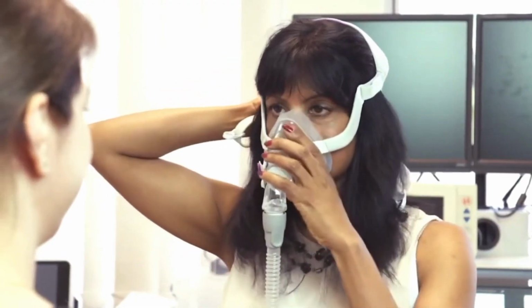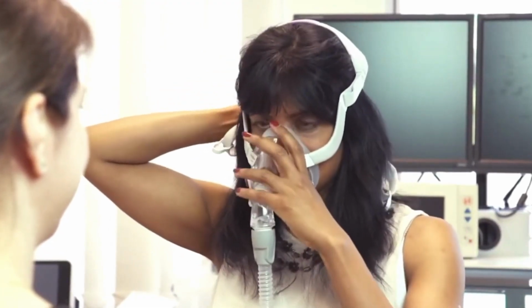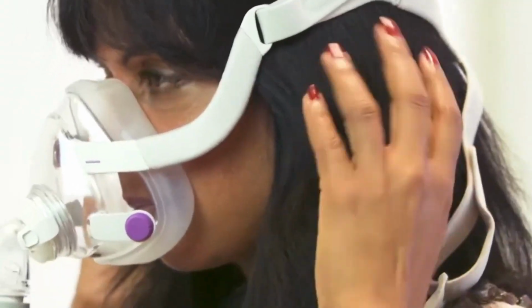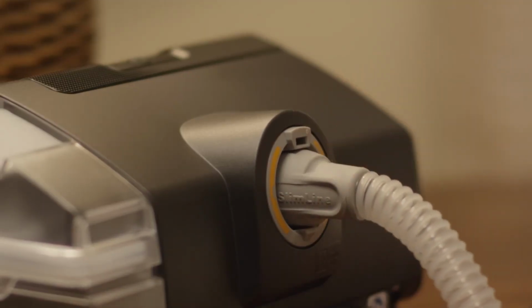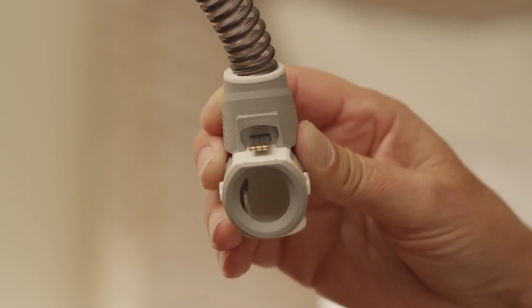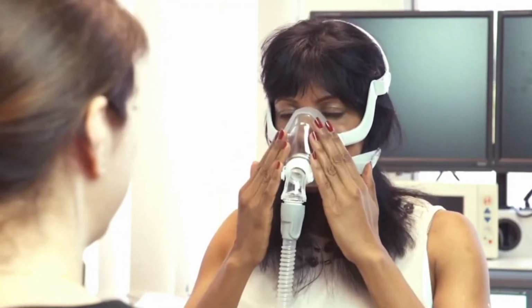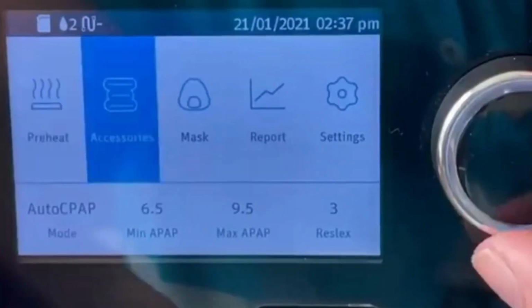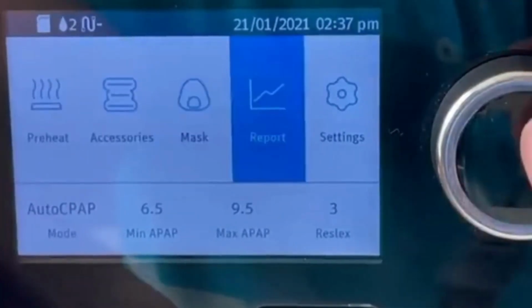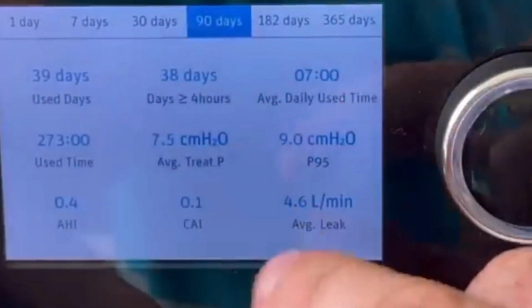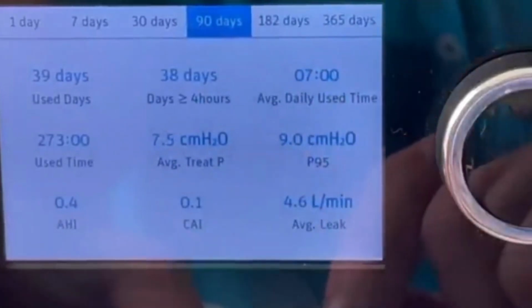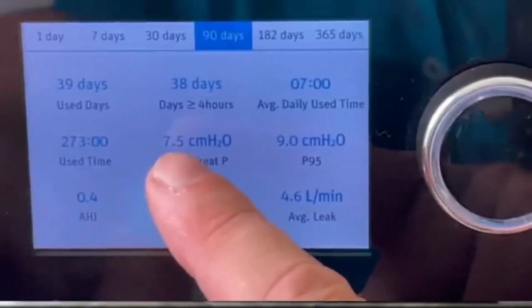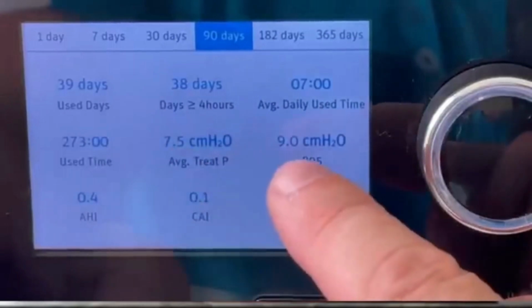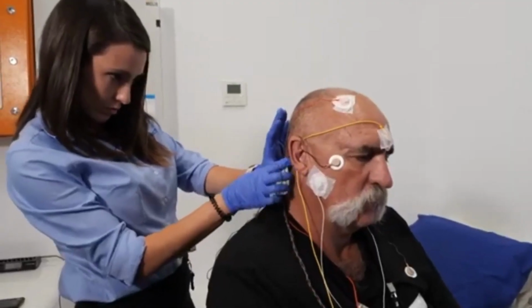The CPAP machine consists of a mask that is worn over the nose or the nose and the mouth, a hose that connects the mask to the machine, and a motor that generates the air pressure. The machine is designed to deliver a continuous flow of air pressure through the hose and into the mask. The pressure of the machine is set by a sleep specialist to the appropriate level for the individual patient, typically around 4 to 20 cm H2O, or centimeters of water pressure, with the average being around 10 cm H2O.